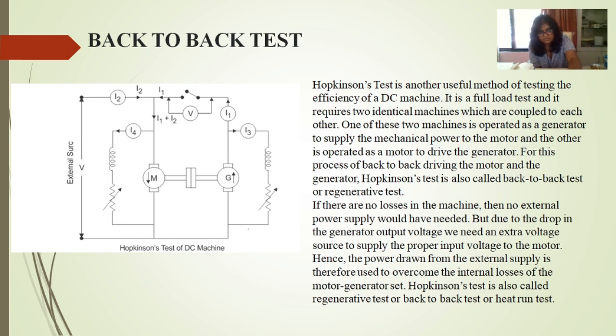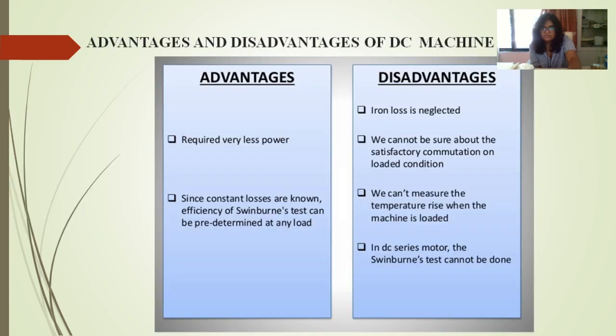If there are no losses in the machine, then no external power supply would be needed. But due to the drop in the generator output voltage, we need an extra voltage source to supply the proper input voltage to the motor. Hence, power drawn from the external supply is therefore used to overcome the internal losses of the motor generator set. Hopkinson test is also called as regenerative test, as I said earlier, or back-to-back test or heat run test. You can reference the figure for extra information.